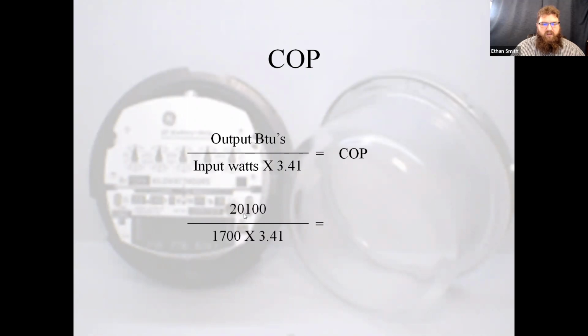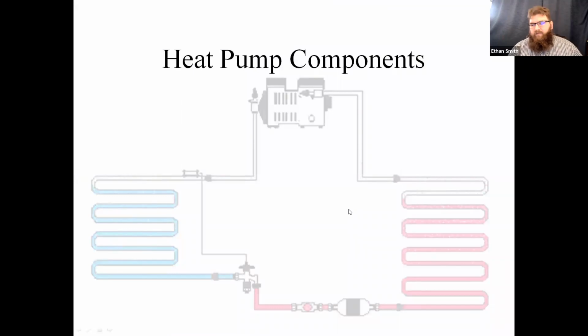So there's my 20,100 BTUs. I take my 1,700 watts. I multiply that by 3.41 BTUs per watt. We find out I get a COP of 3.46. So I'm getting 346% more heat out of this system than if I were to run straight electric, or 3.46 times more heat. Okay, so that's my coefficient of performance. Okay. Any questions about that, guys?